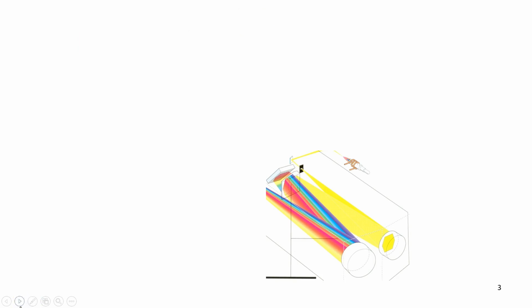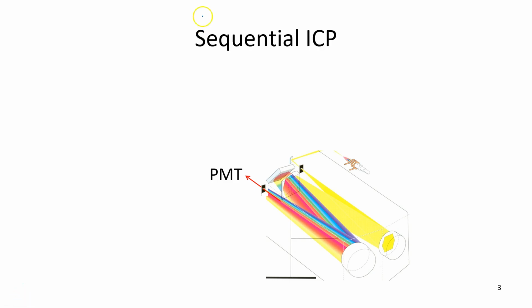If you get rid of your array transducer and instead put an exit slit for a monochromator there, and maybe under these circumstances only this red wavelength is leaving the monochromator, you could have a PMT, a photomultiplier tube there, detecting one wavelength at a time, and that's what happens in a sequential ICP. So maybe this red wavelength is the wavelength for copper emission. You have the grating rotated such that only that wavelength leaves the monochromator.